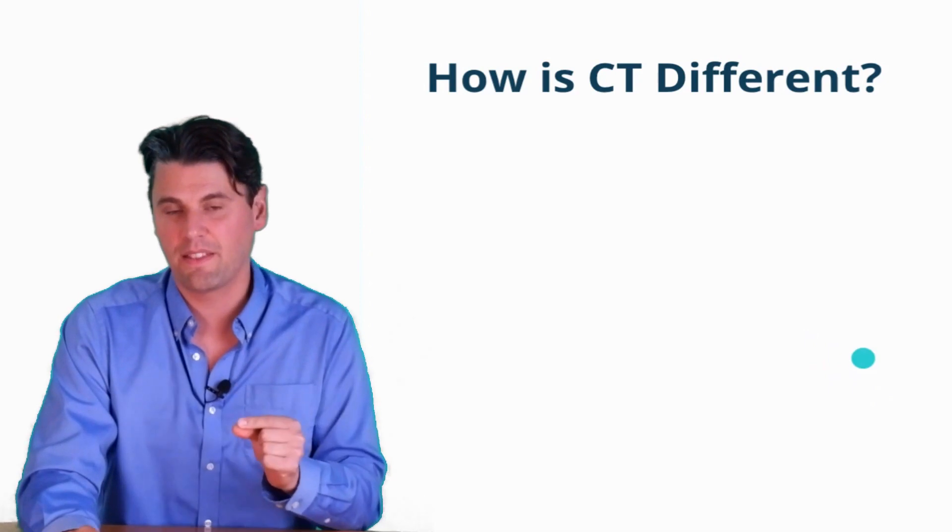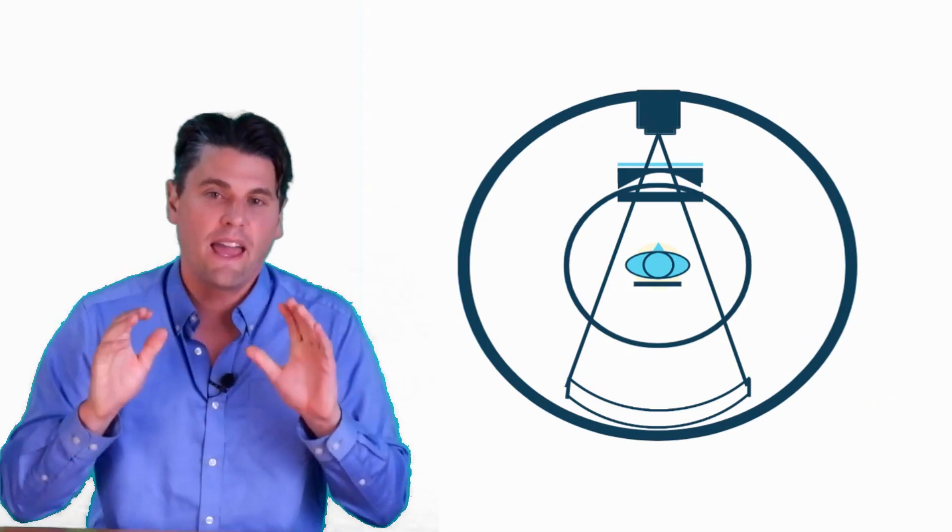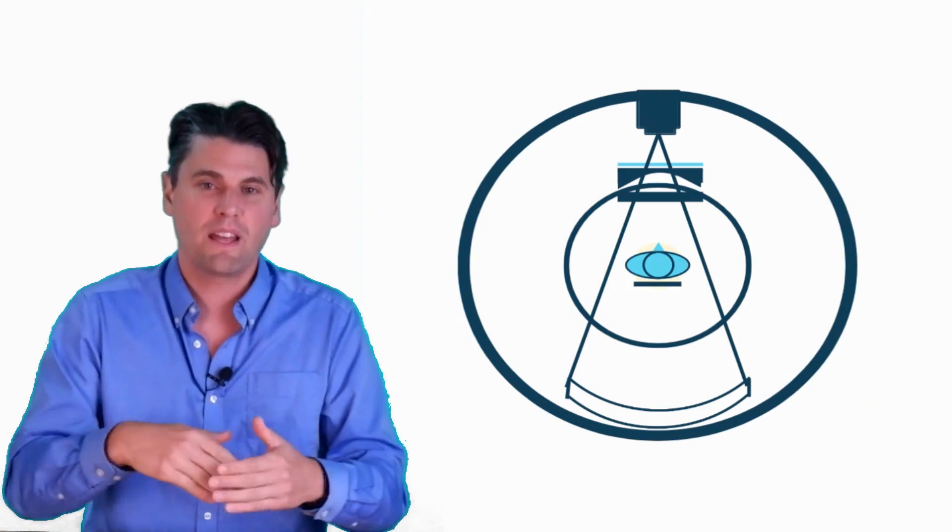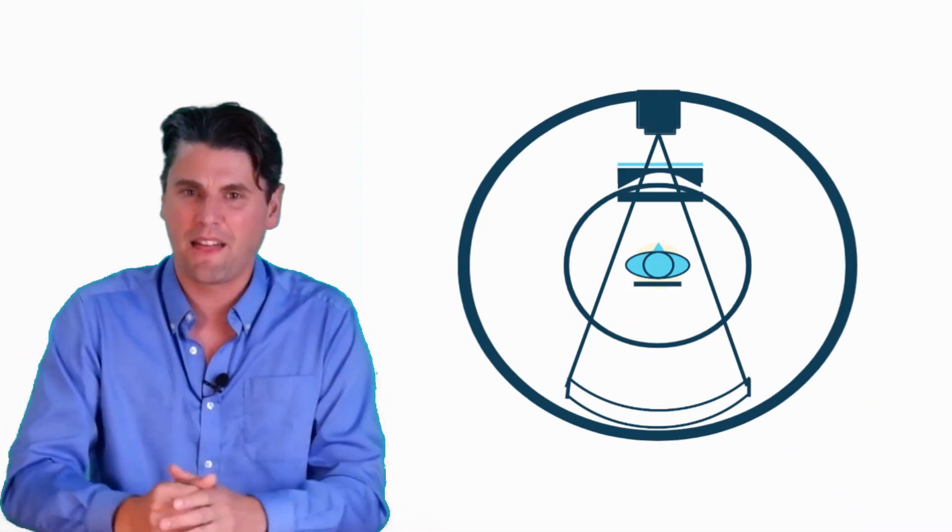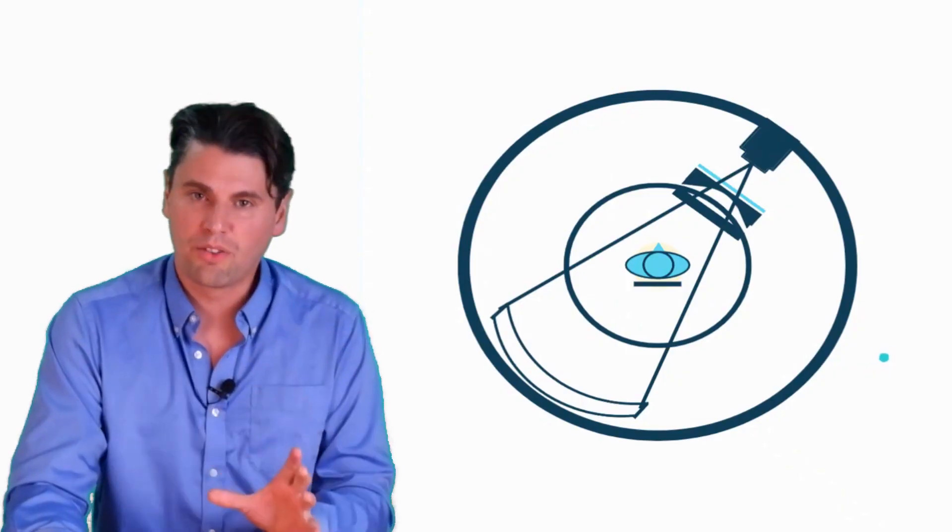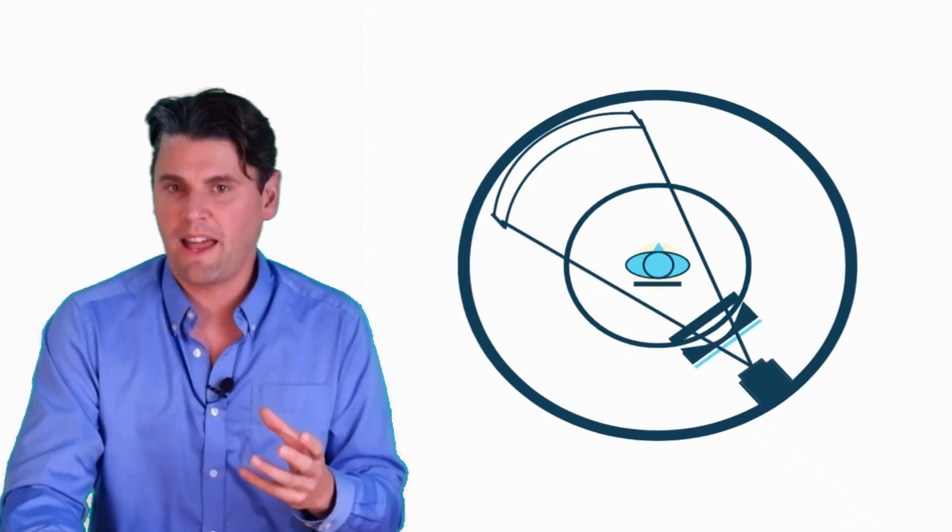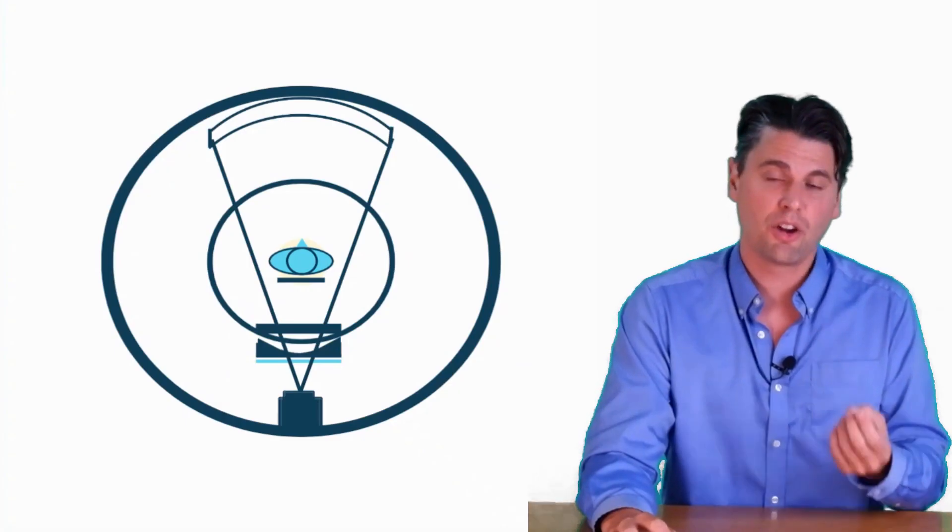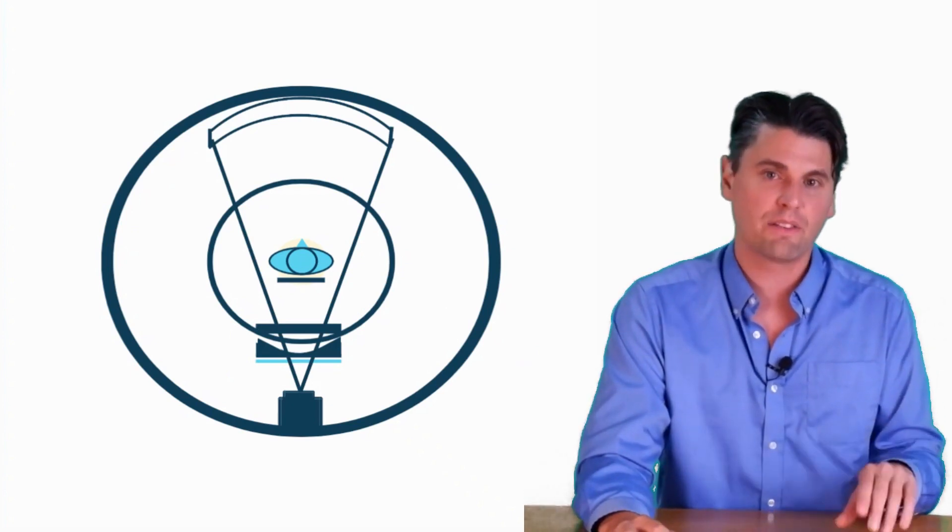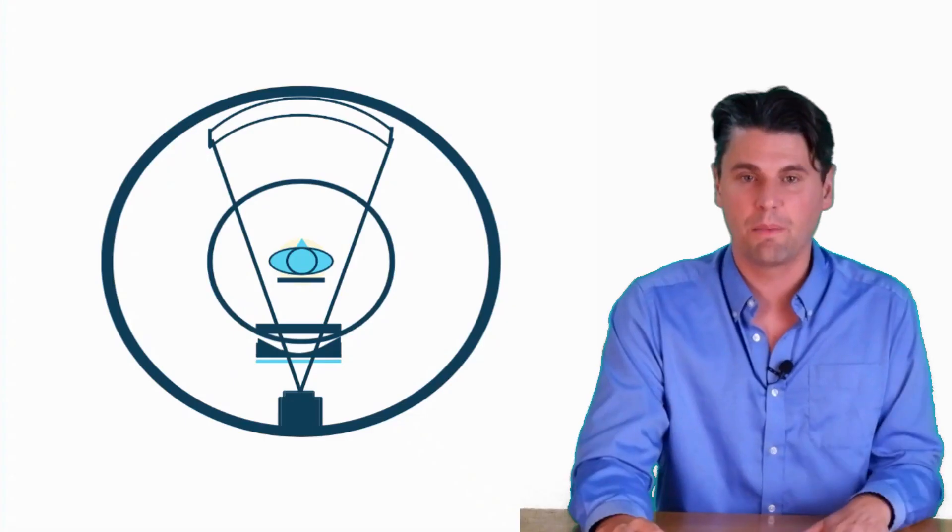And then how is CT different than this? CT, we're actually doing reconstruction. So instead of taking just one picture like we are in x-ray, we're taking many pictures, like around 1,000 pictures at least usually to generate an image. So our source and our detector are rotating around the patient. So if there's motion during that acquisition, it's actually going to show up during that reconstruction process. And it's going to be a little bit different than x-ray because x-ray doesn't actually need a reconstruction process. It just reports the image.